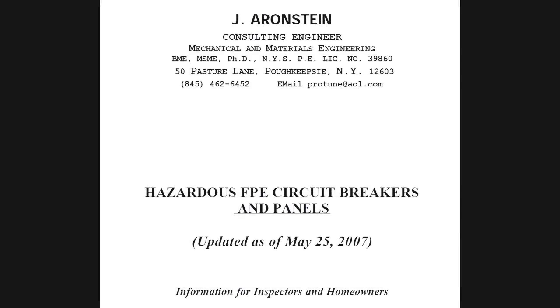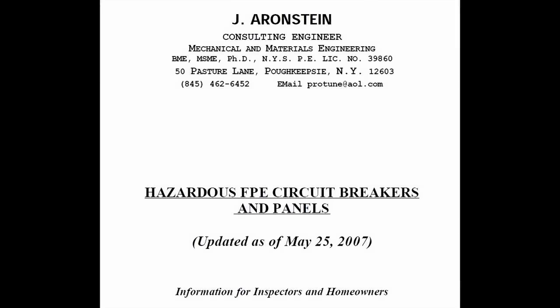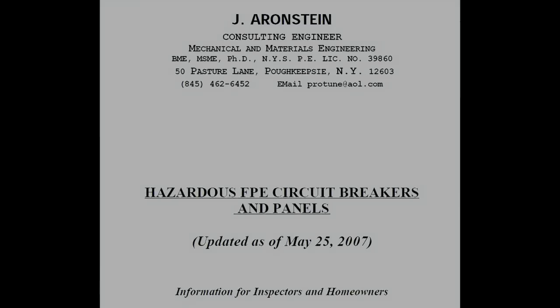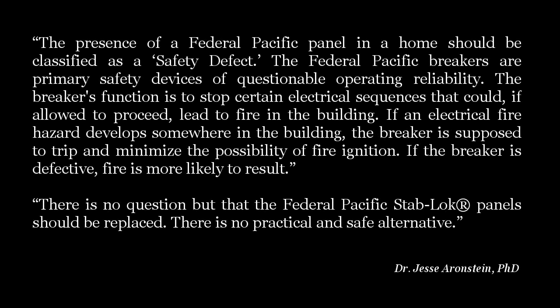In a report to the Consumer Product Safety Commission, Dr. Jesse Aronstein, Ph.D., a consulting engineer specializing in mechanical and materials engineering, stated that the presence of a Federal Pacific panel in a home should be classified as a safety defect. The Federal Pacific breakers are primary safety devices of questionable operating reliability. The breaker's function is to stop certain electrical sequences that could, if allowed to proceed, lead to fire in the building. If an electrical fire hazard develops somewhere in the building, the breaker is supposed to trip and minimize the possibility of fire ignition. If the breaker's defective, fire is more likely to result.